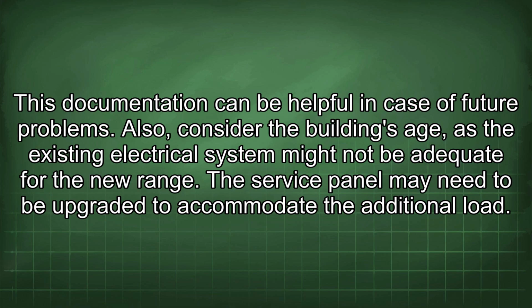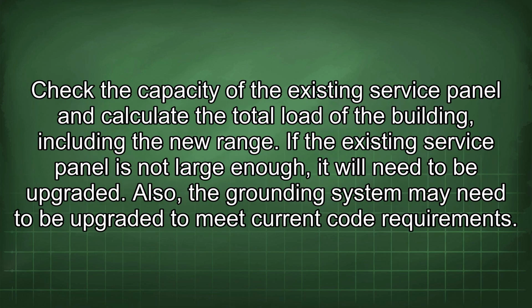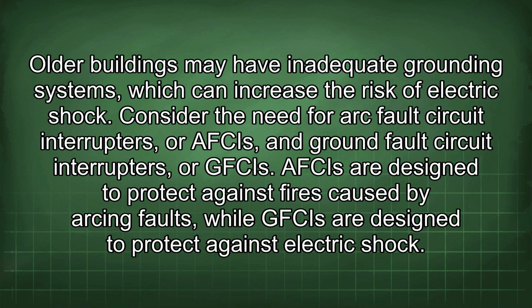Also, consider the building's age, as the existing electrical system might not be adequate for the new range. The service panel may need to be upgraded to accommodate the additional load. Check the capacity of the existing service panel and calculate the total load of the building, including the new range. If the existing service panel is not large enough, it will need to be upgraded. Also, the grounding system may need to be upgraded to meet current code requirements. Older buildings may have inadequate grounding systems, which can increase the risk of electric shock.